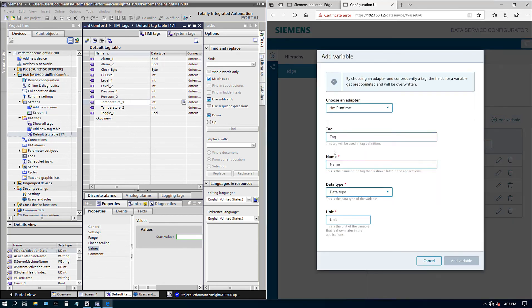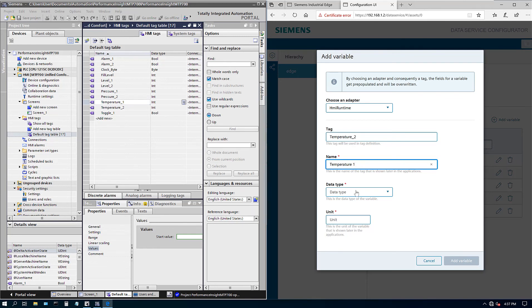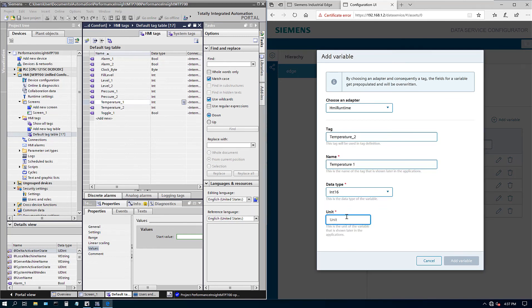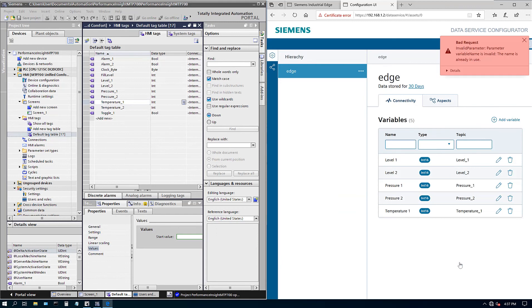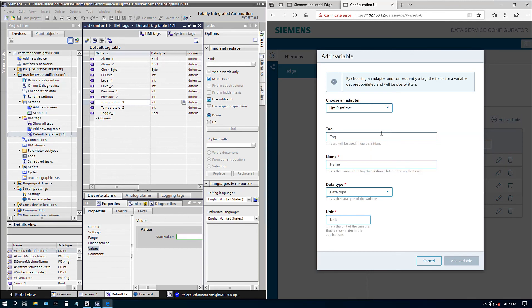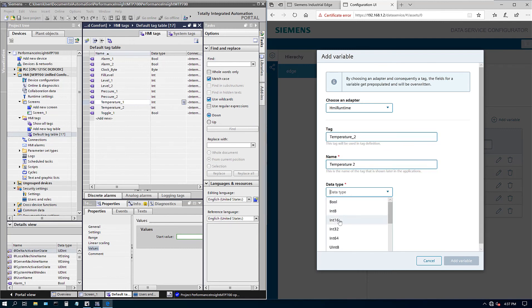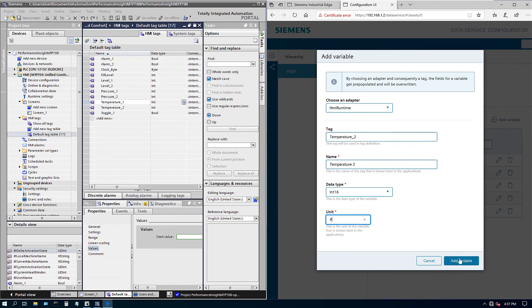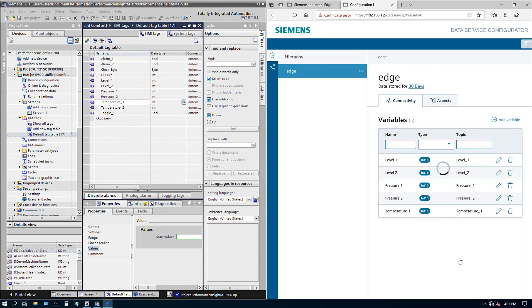And then what do we have? We have temperature. So let's go ahead and add temperature. Temperature one. Integer. Let's say degree Fahrenheit. Let's output capital F for it. We have temperature one. And next one is temperature two for tank two. Temperature two. Integer. And degree Fahrenheit. Add variable. Oops. It's already in use. So I think I messed up a typo somewhere. So let's say temperature underscore two. Temperature two. Temperature two. Integer 16. There we go. All right. So we got all our level one. Level two. Pressure one two. Temperature one two. So we got all our tags.